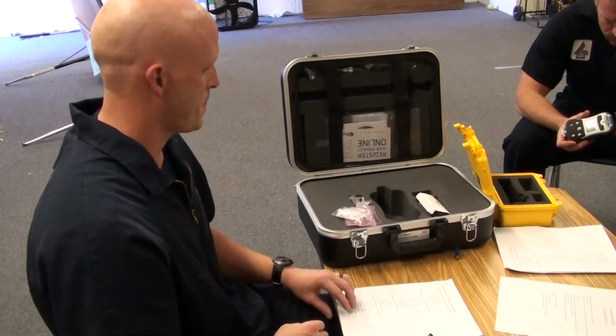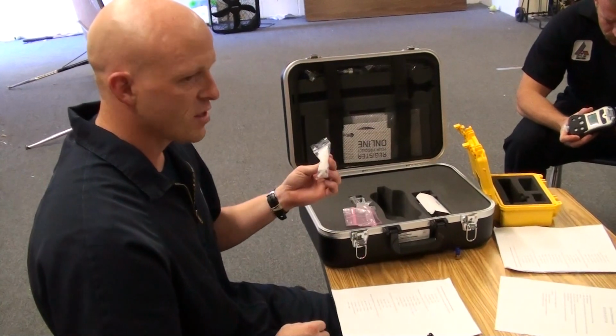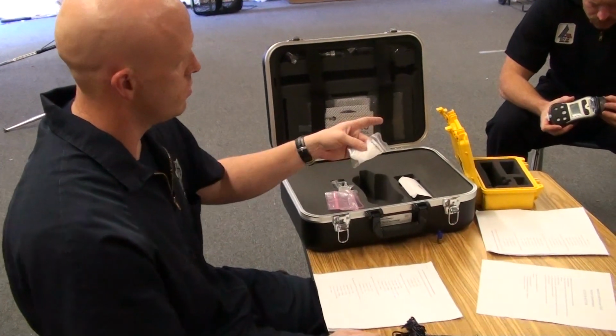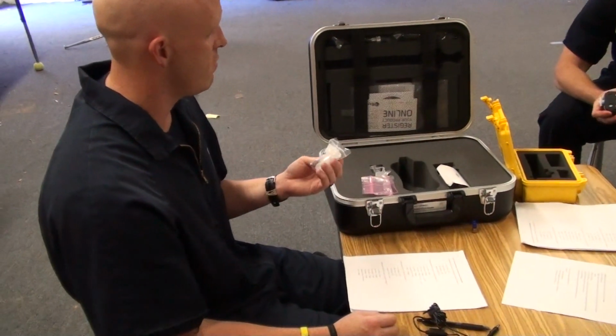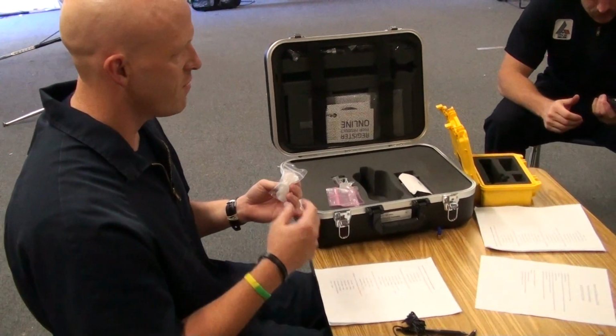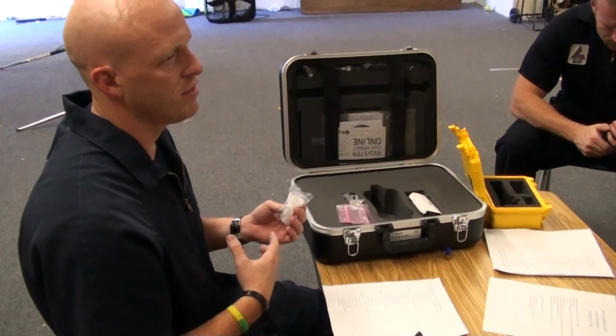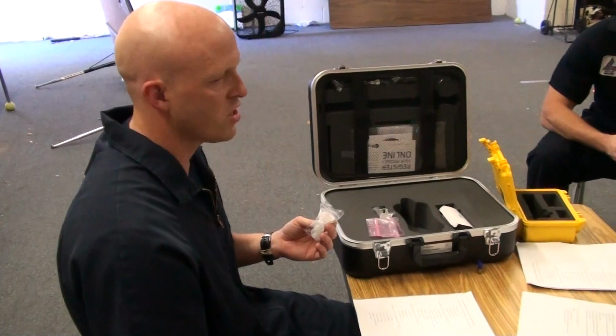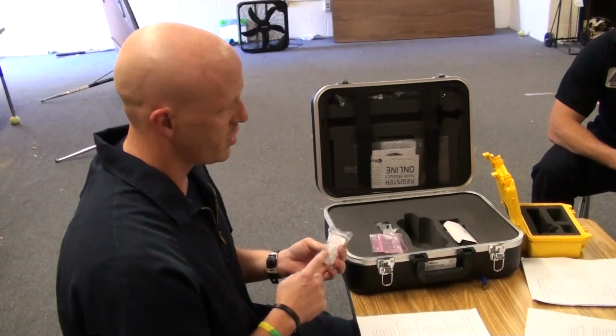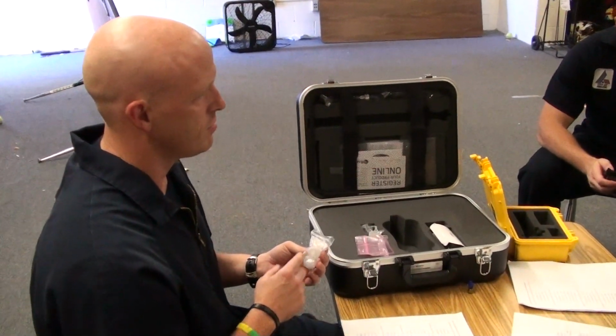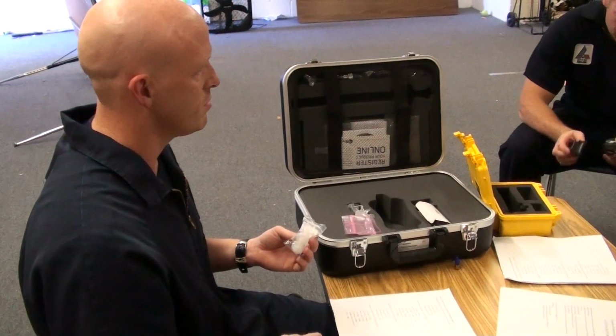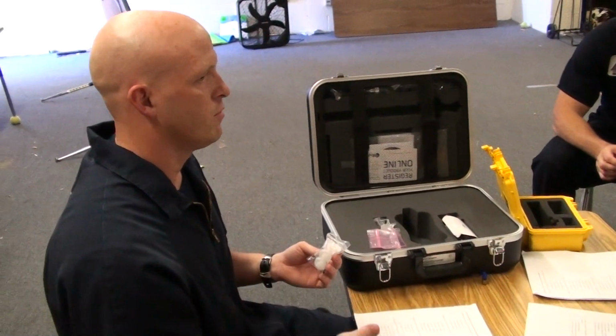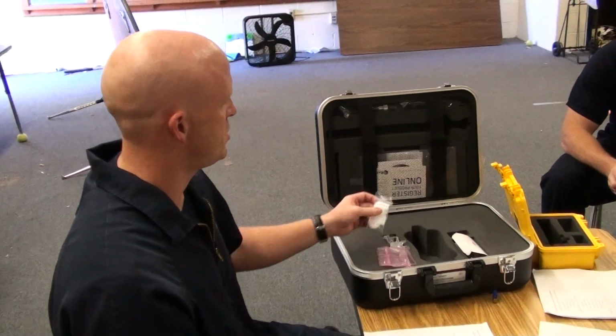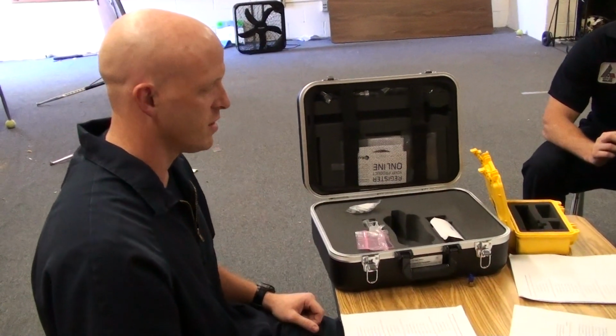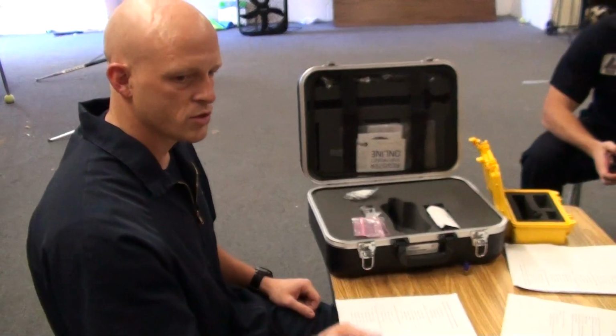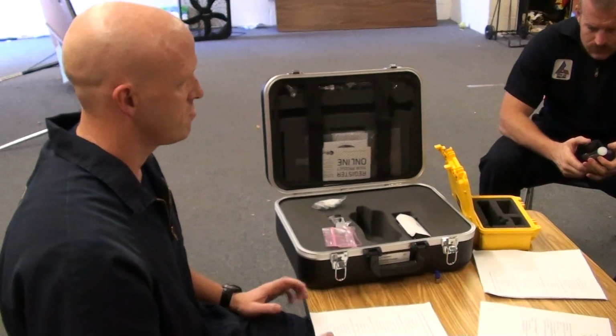The filters on top just screw in. It's a little plastic thing with a white filter on the inside. If anything's malfunctioning, or you're not getting good readings right after your fresh air calibration, these only cost about $2 a piece, so take it off and switch it out for a new one. It's a lot cheaper than replacing a sensor, just the first step of problem solving, and they're interchangeable between each monitor, very simple.